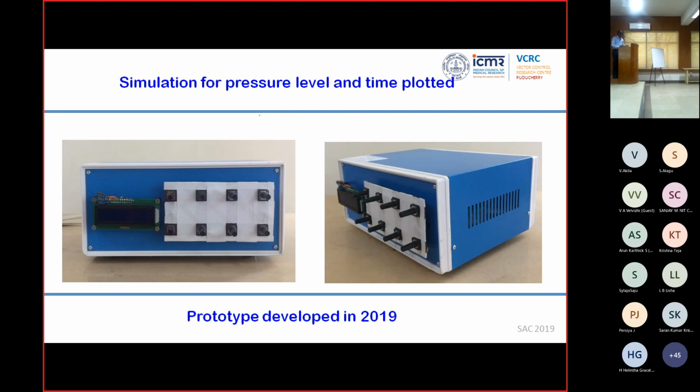So we developed a semi-automatic machine in which the patient can control the pressure in all four channels. But at the same time, we have put an upper limit. The pressure cannot go beyond a particular limit, so even if the patient pushes the button, it automatically gets released. The pressure cannot go beyond that fixed limit. This is the prototype we developed in 2019.